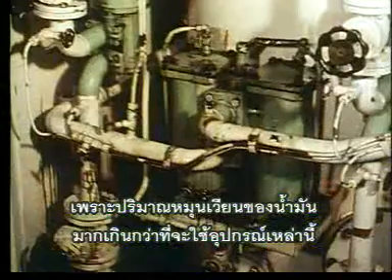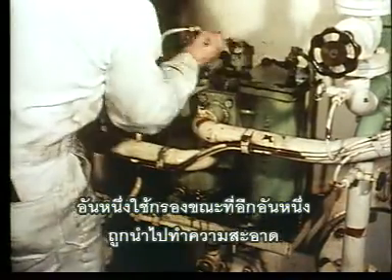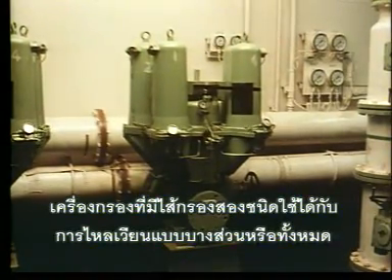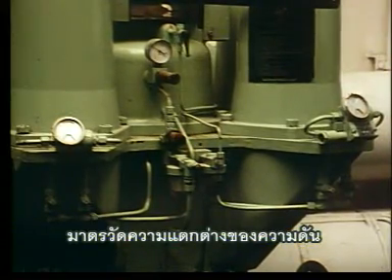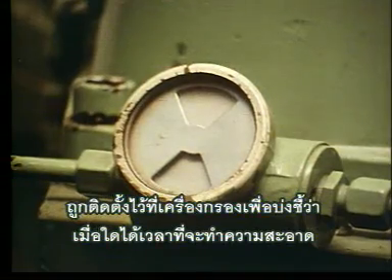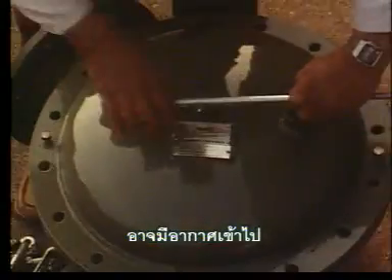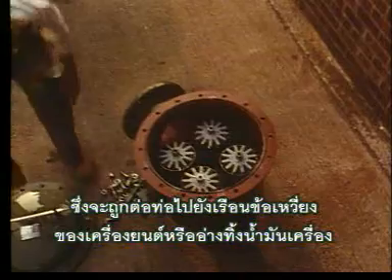in full flow treatment. Duplex or two-element type filters are used, so that one may be cleaned while the other is in service. A dual density element enables the combination of partial flow and full flow treatment in one filter element. Differential pressure gauges connected across the filters indicate when cleaning or removal of the element is required. Some small filters are self-venting, but in the large discharge types, air can collect, and these are vented and piped to the engine crankcase or lubricating oil drain tank.